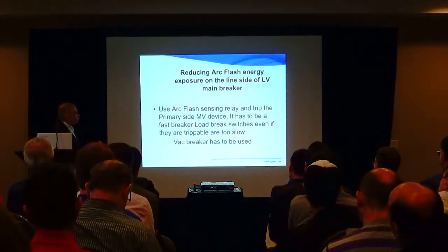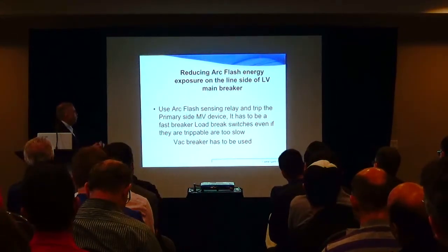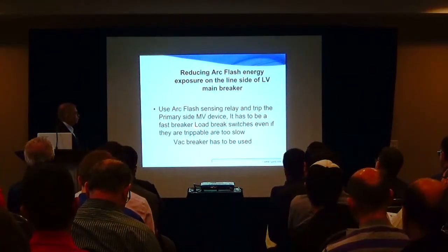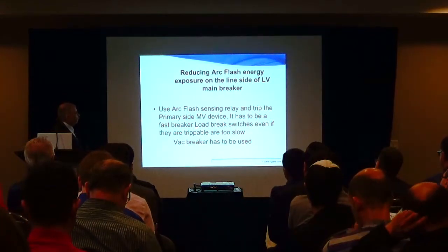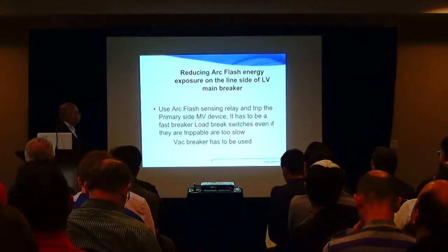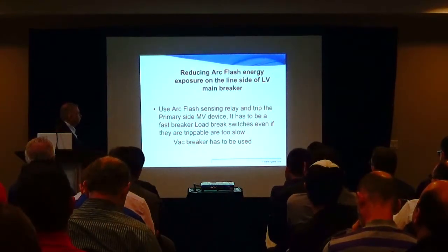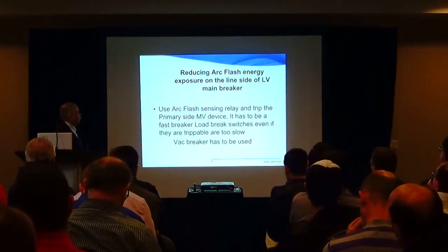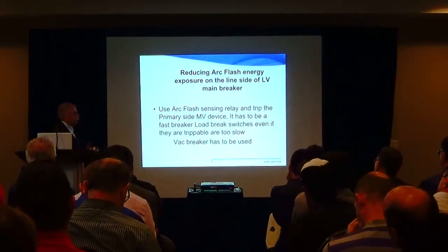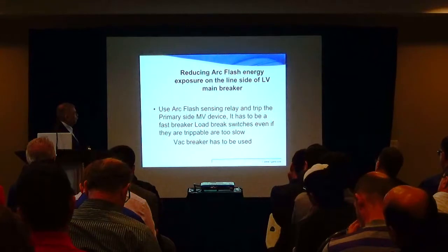Conventionally, we have used load break switches in the past. So we have used 15 kV, 25 kV, 36 kV load break switches. But those load break switches are slow devices, even if they are trippable. First of all, they may be manually operated non-trippable switches, but if they are trippable switches, they take more than 5 to 7 cycles to open. Their arcing time is long, and they are a slow device. So they are not quite satisfactory.